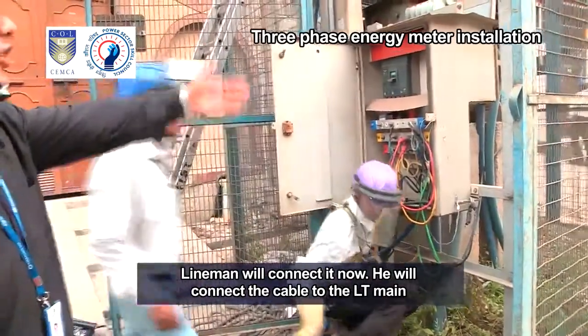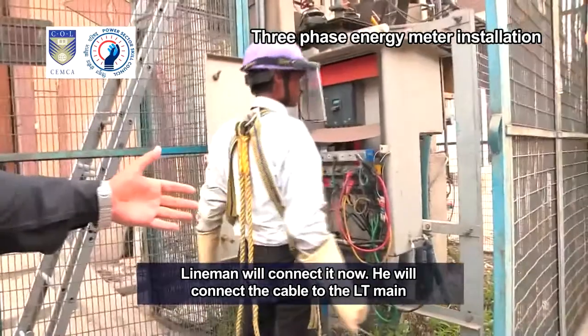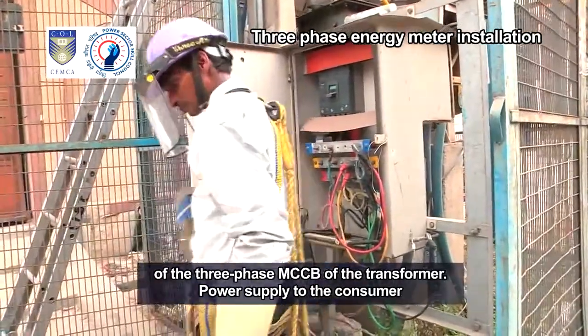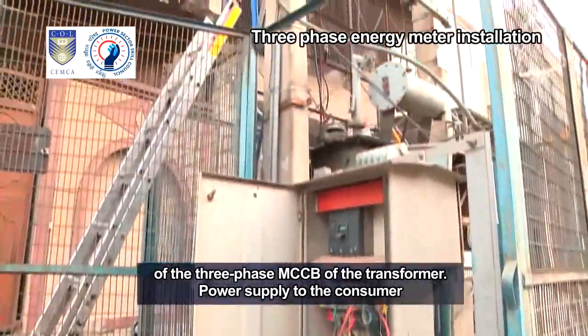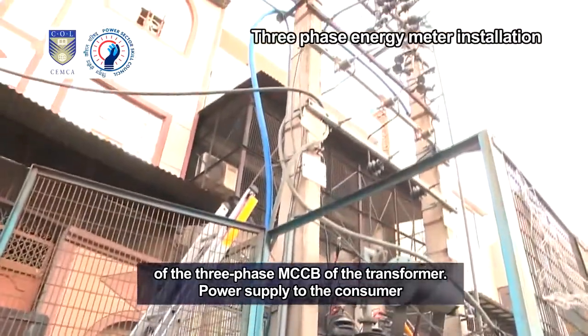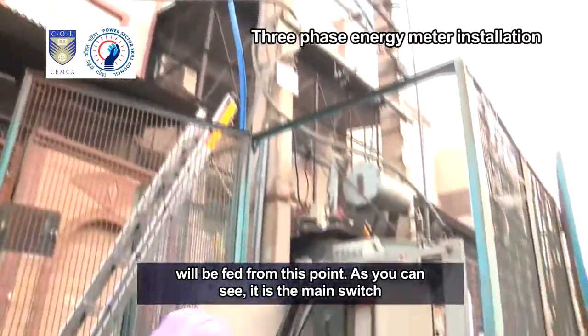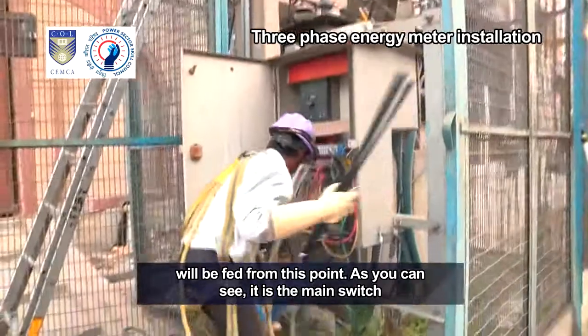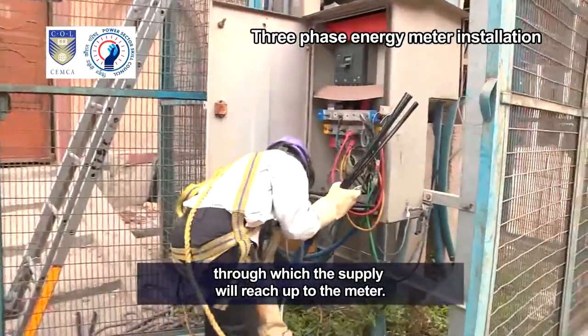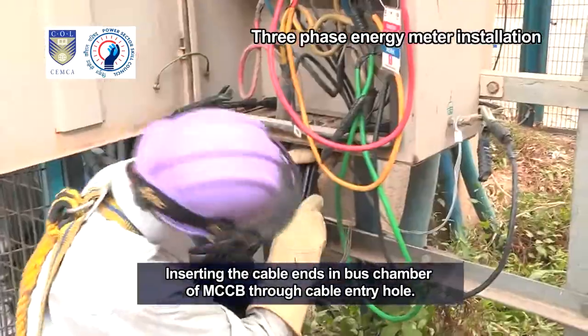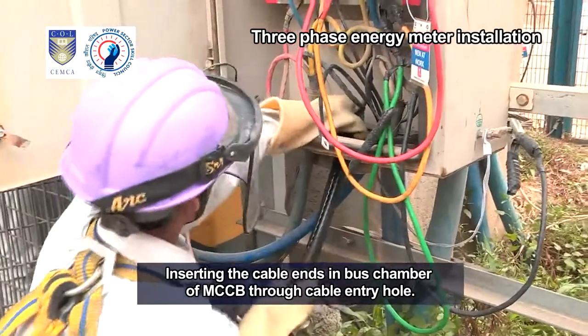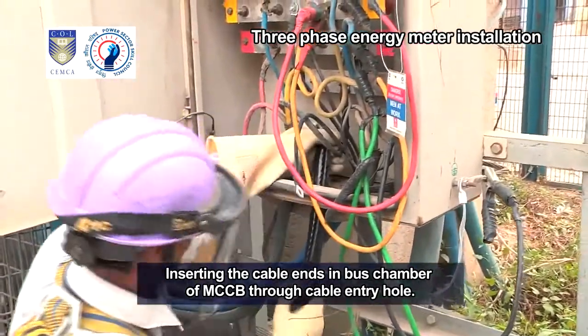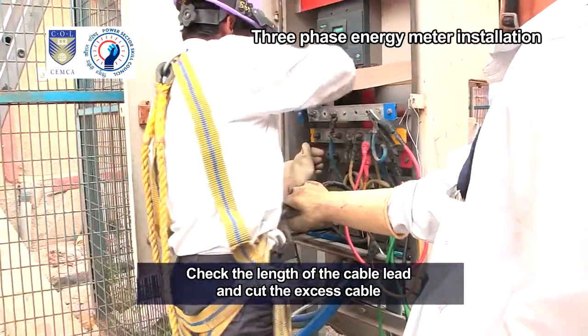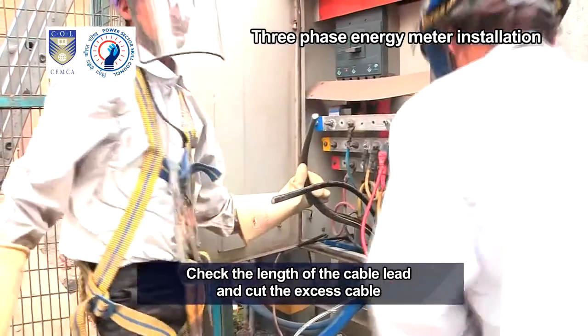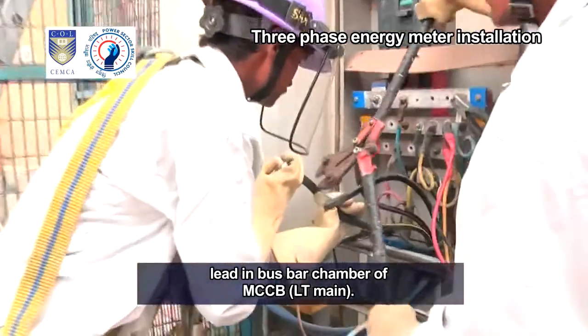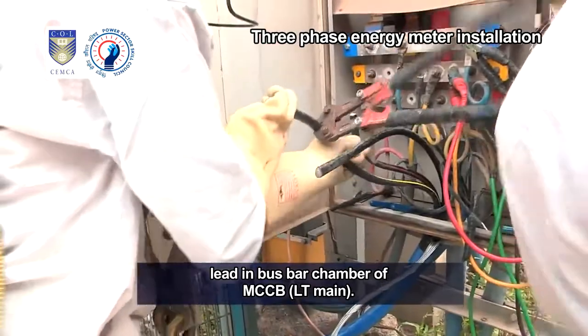Lineman will connect it now. He will connect the cable to the LT main of the 3-phase MCCB of the transformer. Power supply to the consumer will be fed from this point. As you can see, it is the main switch through which the supply will reach up to the meter. Inserting the cable ends in bus chamber of MCCB through cable entry hole.